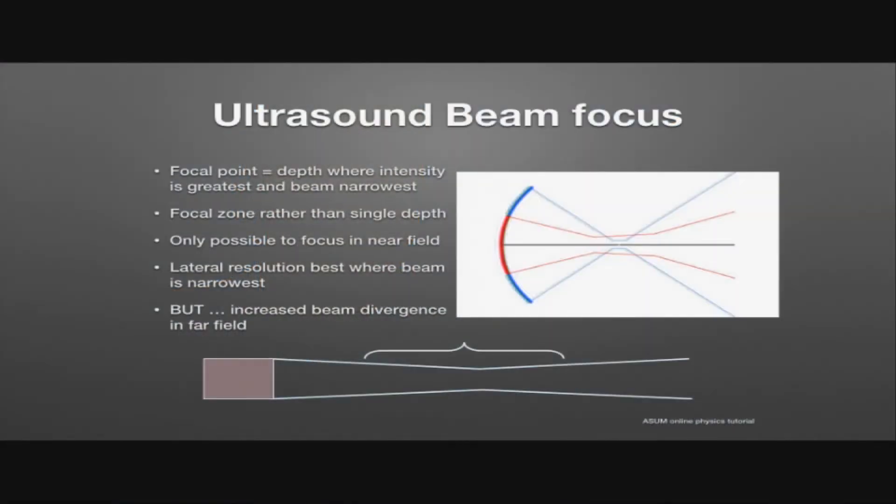Both the axial and the lateral resolution is going to be best where the beam is at the narrowest. But we have to consider that we're going to get increased beam divergence as we go into the far field if we increase the zone of focus. And that's tried to explain in the higher of the two diagrams there, where the focal zone is longer for the transducer in the red versus the transducer in the blue, which has a smaller beam width. So it's going to have better lateral resolution. However, we're going to get greater beam divergence happening in the far field.